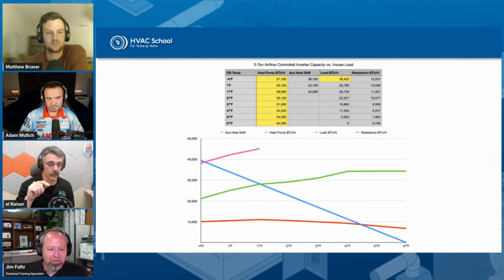And this piece of equipment would work really well for this house. You can see where the green line and the blue line intersect is somewhere around 17 degrees. So that means at 17 degrees, I'm going to run out of heat with that heat pump. I can't heat the house 100% to demand with only the heat pump. But the red line down there, remember, that's my resistance BTU equivalent. That's the equivalent BTUs that would come out of a resistance heater with the wattage I'm running into that heat pump. So I'm still getting way better performance. My COP at 17 was still well above 2 with this unit.